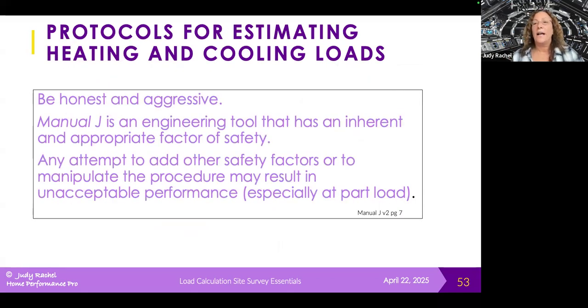So our protocols for estimating the heating and cooling loads. This is what Manual J tells us. It says to be honest and aggressive. It tells us that Manual J is an engineering tool, and it has an inherent and appropriate factor of safety, which I'll talk about in a second. And any attempt to add other safety factors or to manipulate the procedure may result in unacceptable performance, especially at our part load conditions. So there's a lot of myths out there about safety factors in the load calculation procedure.